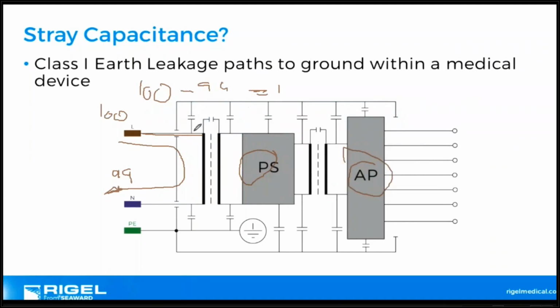Well, if I've got any leakage current, it's due to the stray capacitance, because remember, AC capacitance. Apologies, my drawings are terrible. I'm using a mouse. I need to get something a little bit better. Anyway, this stray capacitance, because I've got conductor current, it's just going via these capacitors, and then flowing to the protective earth, and this is where the 1 milliamp ends up. So it's kind of like you've got your conductors, you've got your insulators. By the definition of a conductor and an insulator, you have a capacitor.